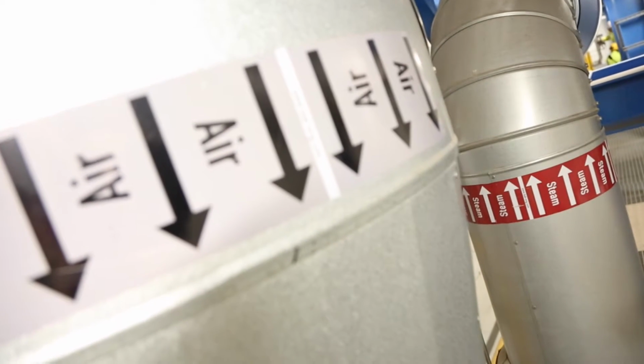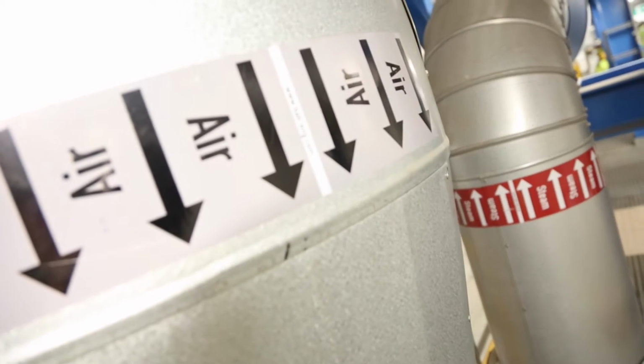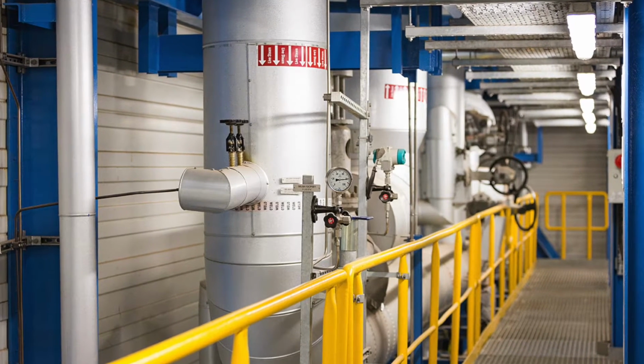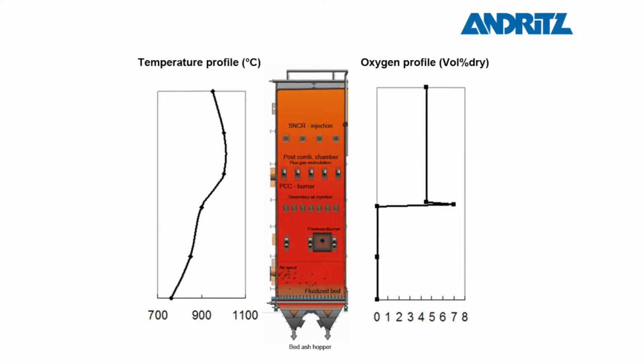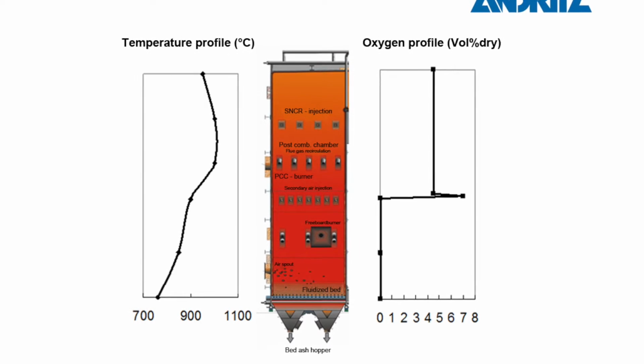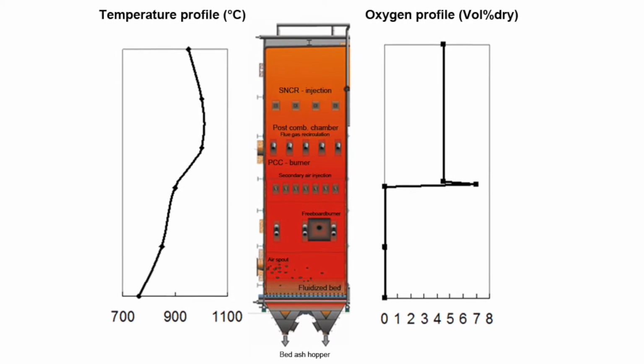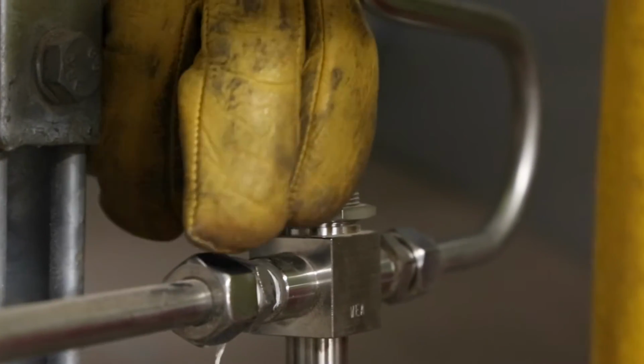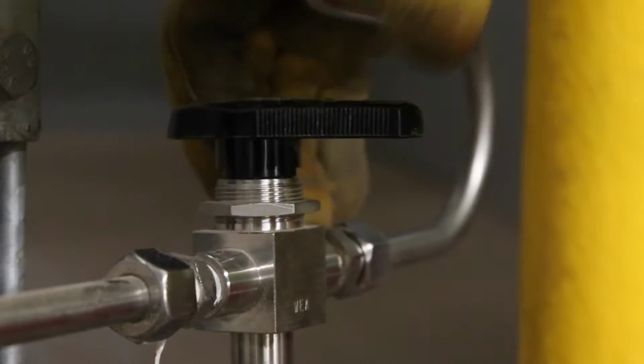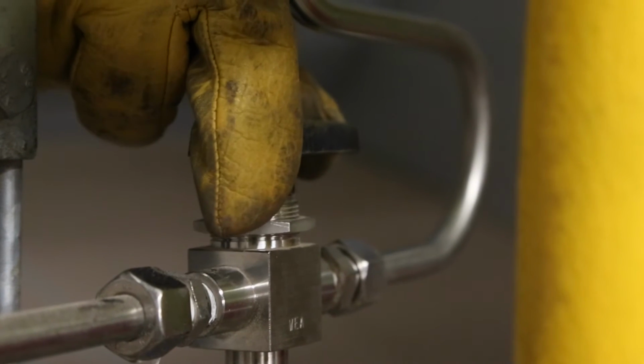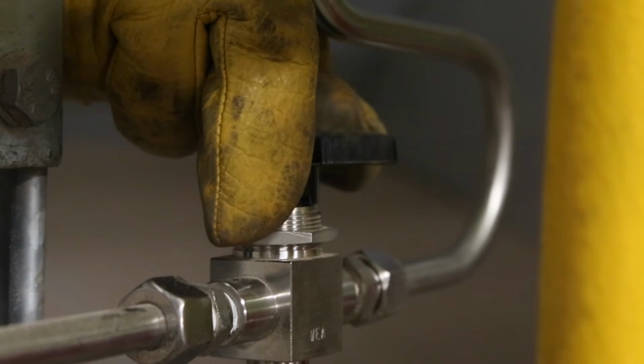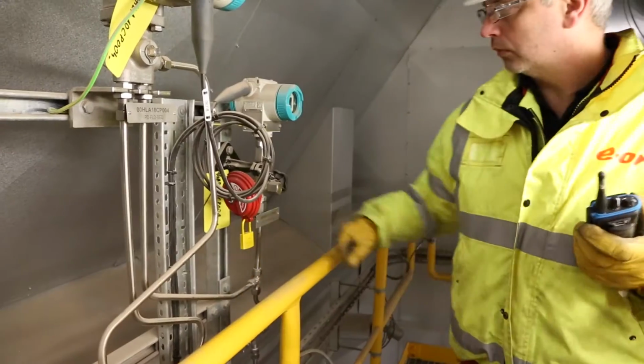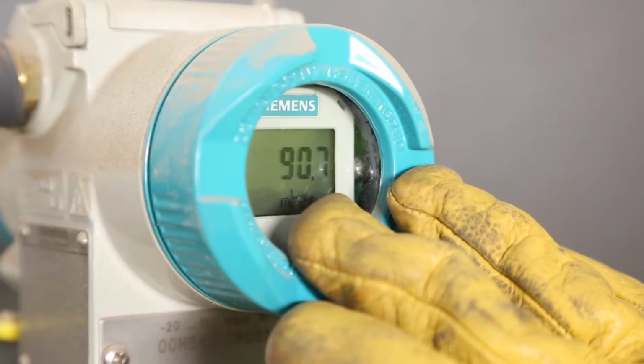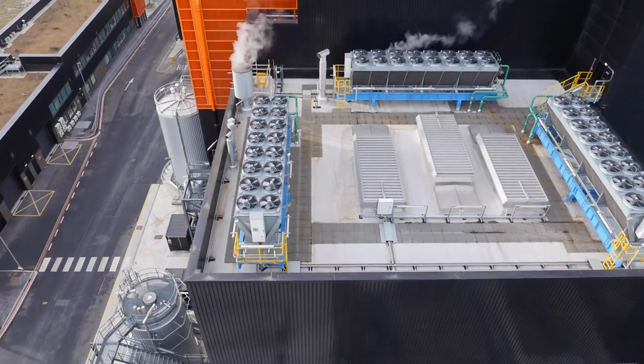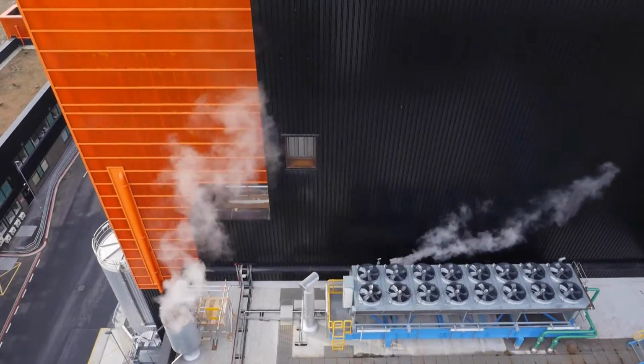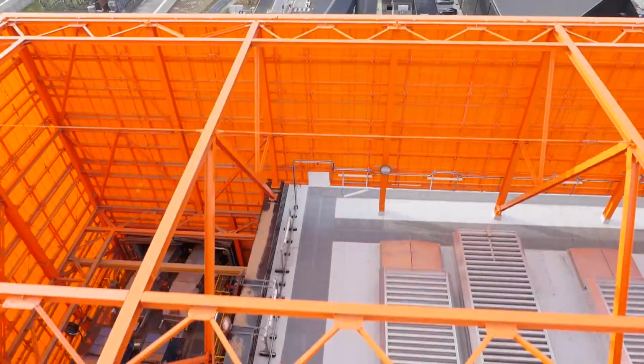The gasification gases rising from the bed are fully combusted by injecting secondary air into the post-combustion chamber. This causes a rise in temperature and oxygen content, as seen in the diagram. The turbulence in this area of the first pass results in very low CO values in the flue gas. For high calorific fuels, recirculation gas is injected above the secondary air to cool the flue gases in the post-combustion chamber. The Blackburn Meadows plant is based on the bubbling fluidized bed technology, firing recycled wood.